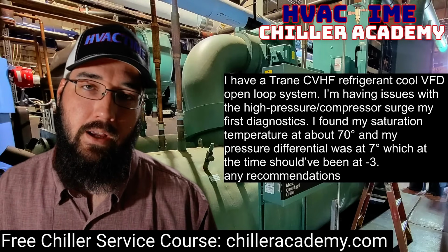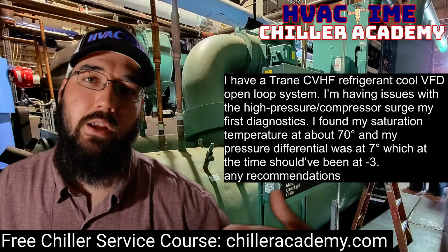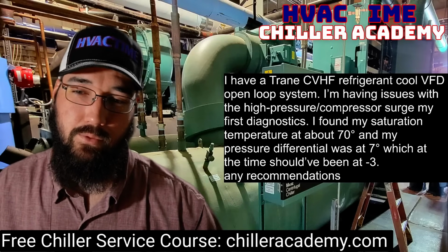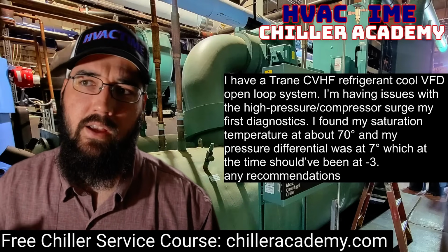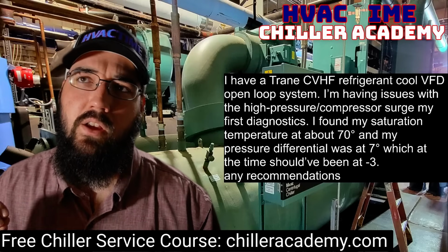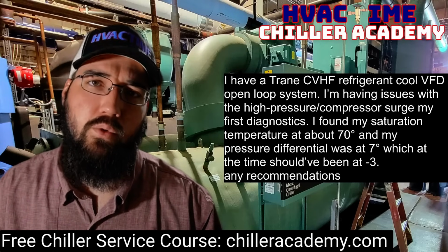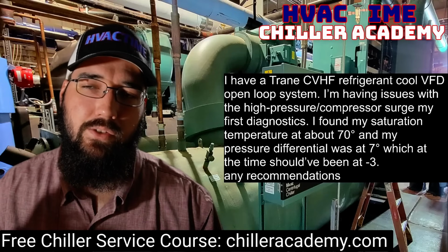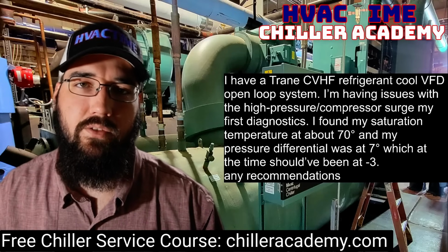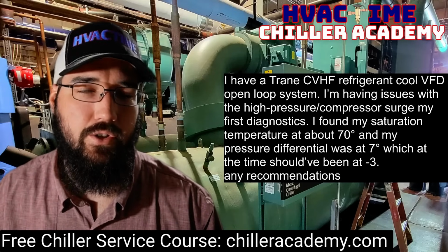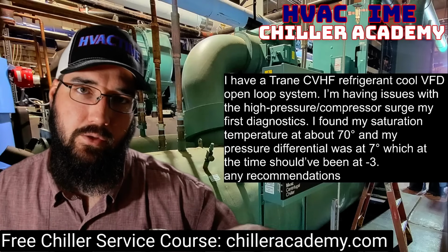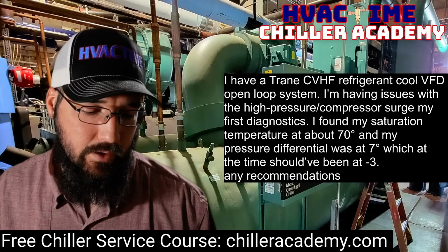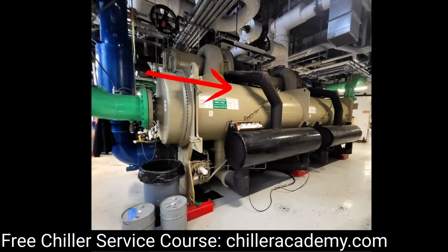Now, keep in mind that if you're keeping the chiller online and allowing it to run, which you mentioned you let it run for about 20 minutes, the onboard purge is only the most effective when the chiller is actually online and running, because they're pulling at a midpoint on the condenser. So if we come back over here, you can actually see the purge vapor line. You can see the isolation valves here, right?